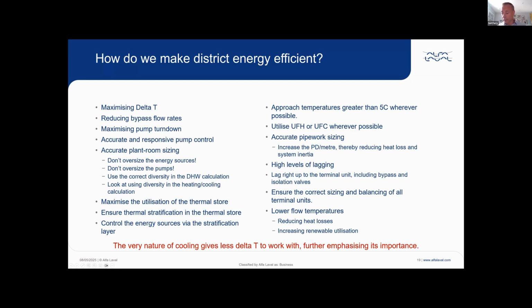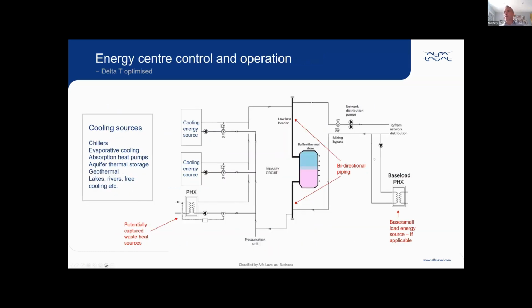One of the issues, of course, with low delta T, it's bad on a heating circuit, but it's even worse on a cooling circuit, because you're already starting with a relatively low delta T that we need to maintain, that we need to not lose any of that if possible, because you have that lower delta T to play with. So when we look in the plant room area, I've given a generic plant room here where we're capturing cooling from different sources. So it could be maybe from free cooling somewhere, different applications. It could be absorption heat pumps that are capturing the waste heat and putting it into the system. And then you could have more traditional chillers and whatever cooling sources here. But the point of this graphic is, hopefully from the last slide, you got that we need to maximize that delta T on the network. So we've maximized this here. What we don't want to do at that point is then destroy that good work, that big delta T, by not controlling in the plant room correctly, or not hydraulically connecting things correctly, and we then destroy what we've struggled hard to achieve on the network.